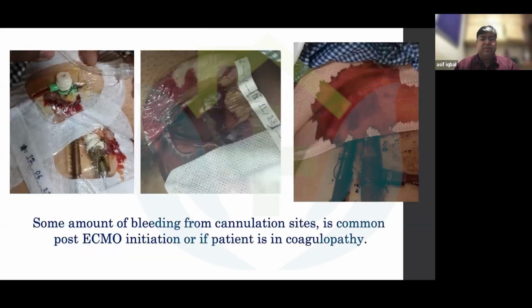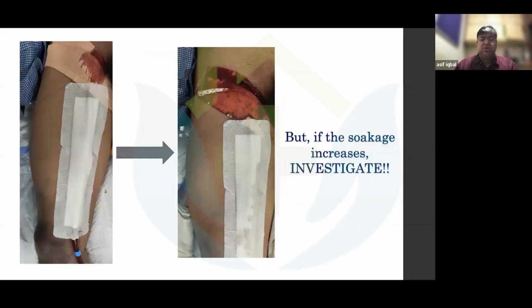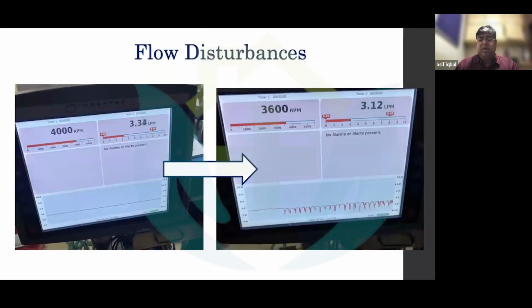The other problem is coagulopathy and bleeding. You have to monitor the ACT, adjust the dose of heparin, and check which parameter is the problem. Another problem is flow disturbance. On the console monitor for the ECMO you can directly identify it by seeing a zigzag ECG-like pattern of the flow. Otherwise, normally it is a linear pattern, like fine VF or a straight line.